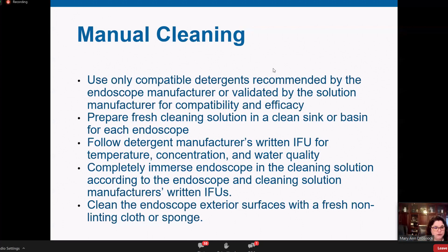Follow your detergent manufacturer's instructions for what temperature it should be used at. You need to monitor that. Make sure that it is appropriately diluted per the IFU or per that label of the detergent, and what quality of water you should be using. Make sure that it's completely immersed under the level of your detergent and water solution in the sink. I know that sounds intuitive, but I was just at a facility not too long ago where there was not nearly enough water to fully cover that endoscope for cleaning. And make sure we're wiping down the outside surfaces of that scope with a fresh, so new every time, single use, non-linting cloth or sponge to do the external wiping parts of manual cleaning.